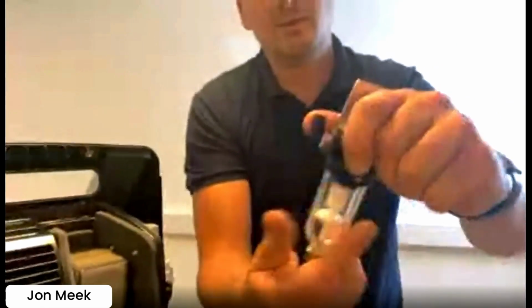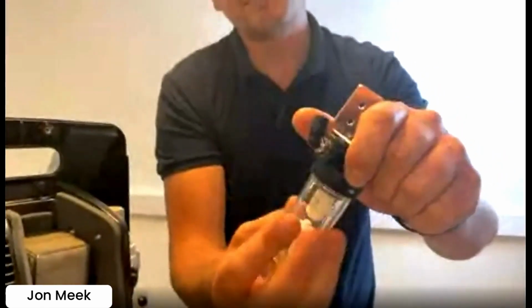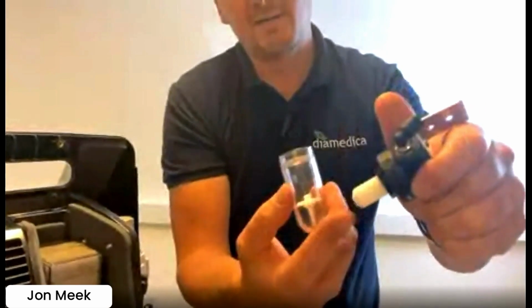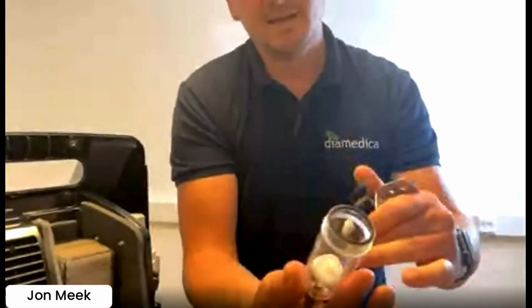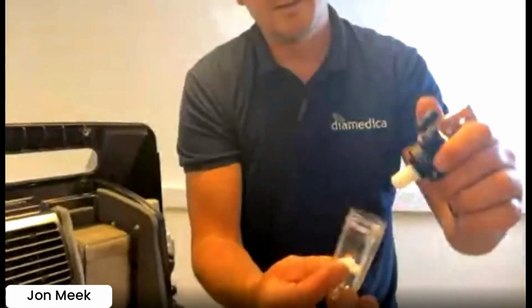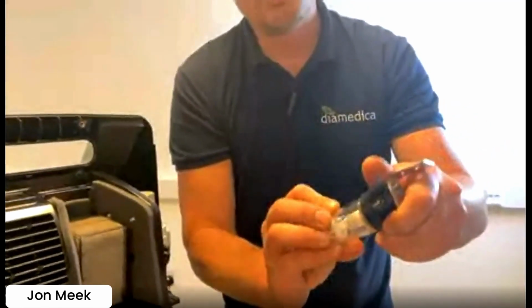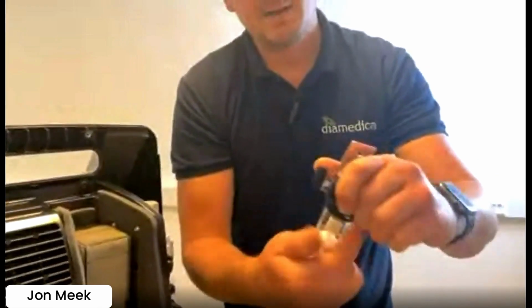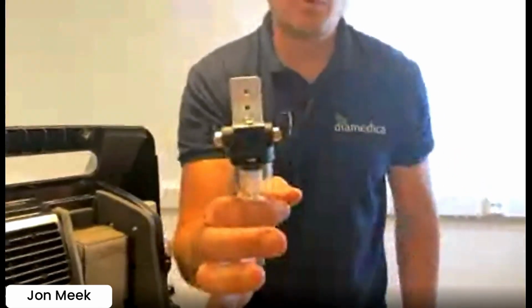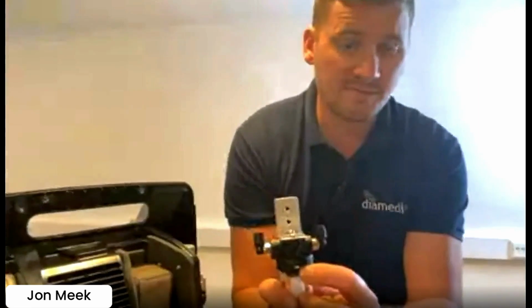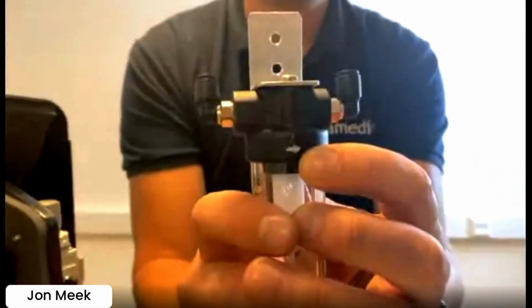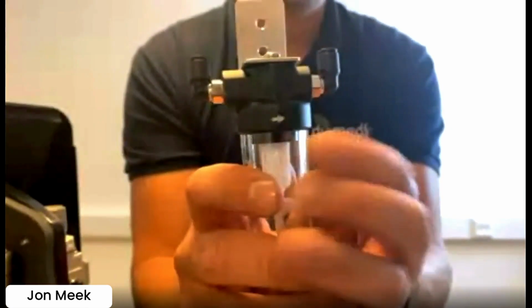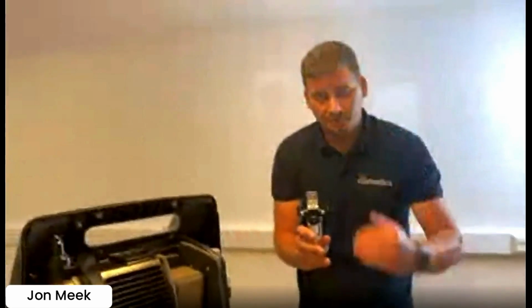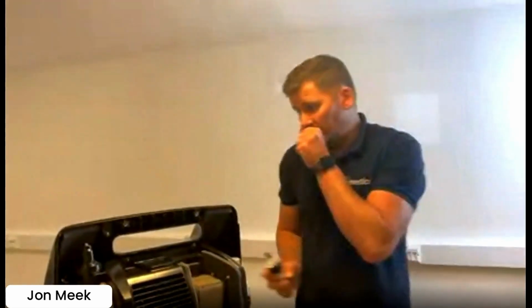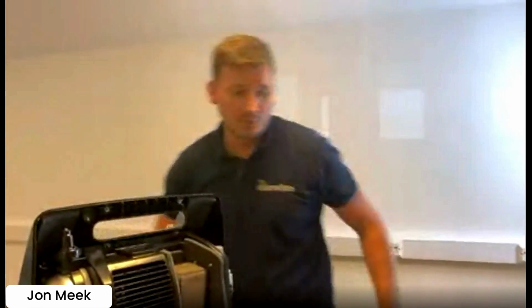And if you need to, you can unscrew and disconnect, and you have a filter in the bottom and the little piece that lifts in the bottom there. But very simple, auto draining. You should never have to take these out as they will auto drain on their own. They have got a direction of flow. So if you ever take any of them out, it only works in one direction. So if you don't have it going the right direction, it will not remove moisture, and it will leave the moisture in the system, which will affect moisture in the flow meter.